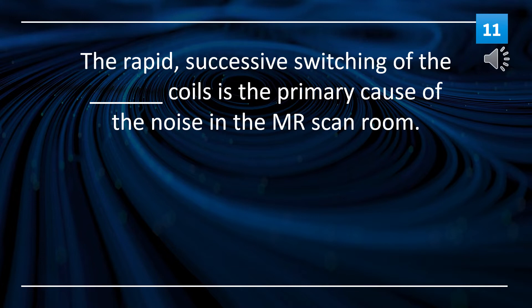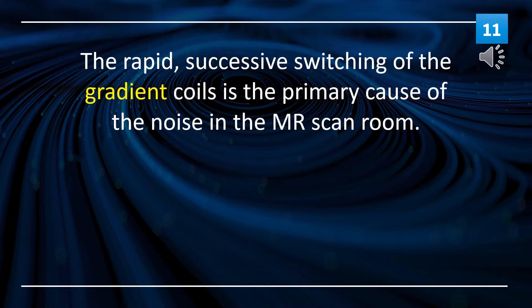The rapid, successive switching of the gradient coils is the primary cause of the noise in the MR scan room.